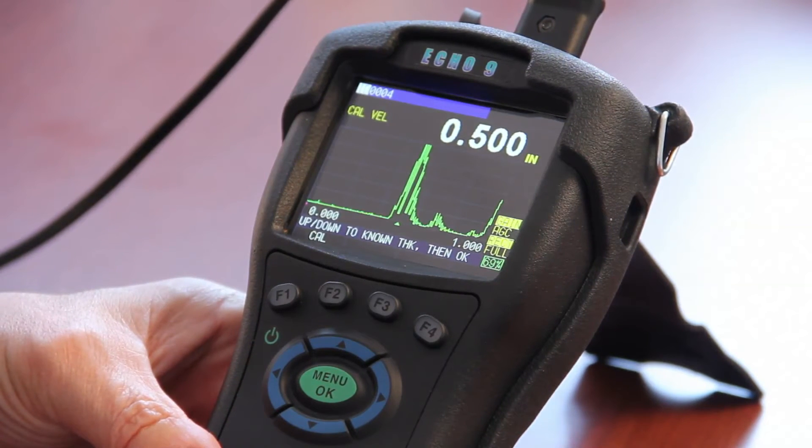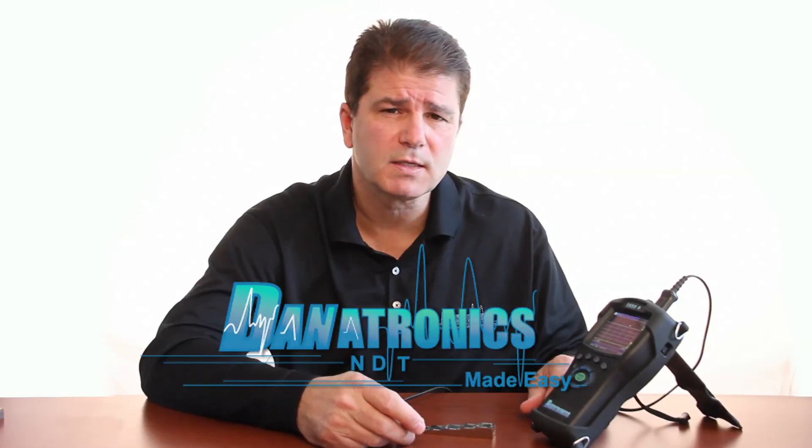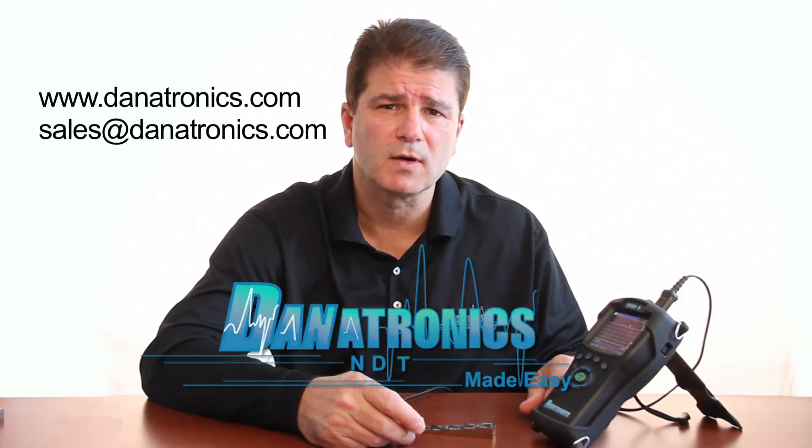At that point you can press the menu OK key and the Echo will display in the top left the acoustic sound speed of the test block. Now I'm ready to go. You can see the values are all within a thousandths of an inch up and down the test block. For more information on the Echo 9 series, contact Danatronics at danatronics.com or sales at danatronics.com.